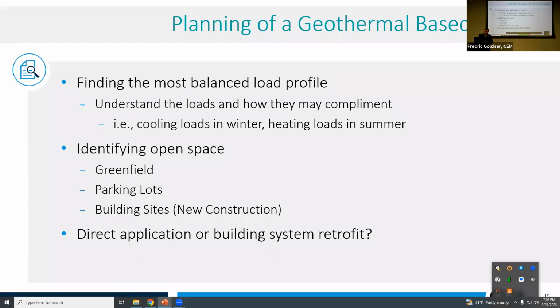Even steam isn't really going throughout the buildings much anymore. It's usually coming into the mechanical room across a heat exchanger. People are working with hydronics now, chilled water and hydronics. So the ability for us to flip an existing building over to geo is relatively simple. An air handler can be repurposed just by swapping out its coils, its heating coil or its cooling coil. We can match them one-to-one with our own geothermal compressors, and now I've got all this added capacity for cooling and heating.